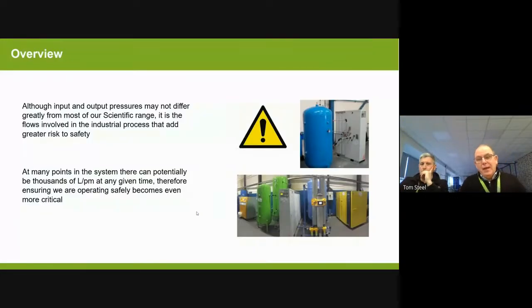Right, safety, guys, I can't emphasize this enough. Safety is hugely important. Where concentrators have been using relatively low pressures and very low flows, we are now talking about over 100 PSI of pressure, 7 bar going into the system, and we are talking from 700 litres up to 4,000 litres. So you have to take care with safety.